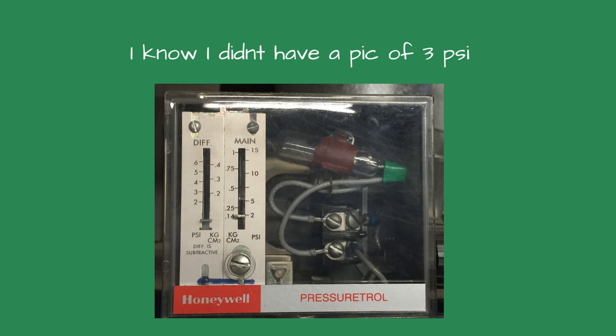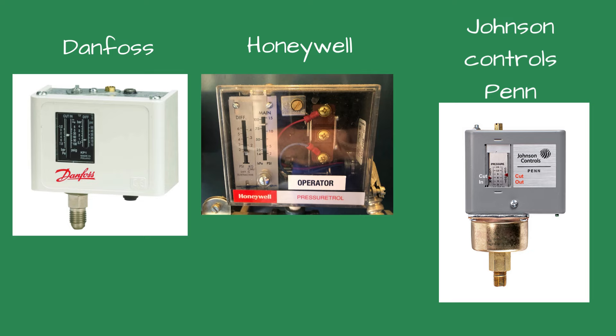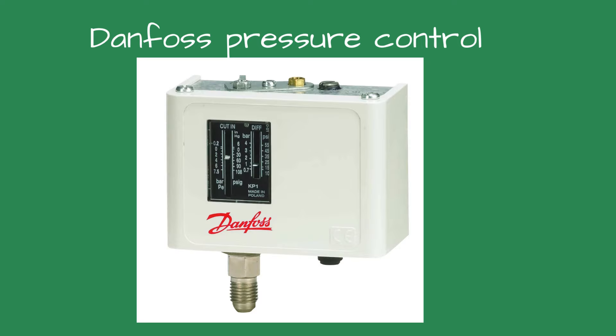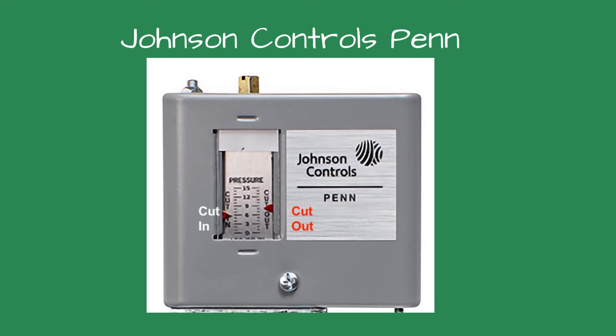For a space heating application, I set the pressure to cut out or stop at 3 PSI and a differential of 2 PSI. The boiler will operate between 1 and 3 PSI for an average steam pressure of 2 PSI. The following controls fall under the subtractive type of pressure control.